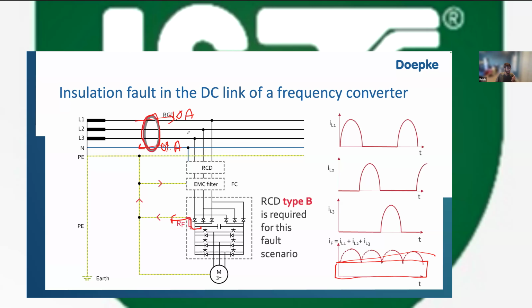Because a type AC and a type A RCD rely on a conventional toroid and the presence of an alternating current at the rated frequency of 50 Hertz, that is why they can trip. They are a very simple device. They just have a toroid that sits around the conductors, and when there is a current, it disconnects. That's it. So to answer the question, a type AC or a type A RCD will essentially get magnetized. It will not be able to trip because there is no changing magnetic field created by the residual current.